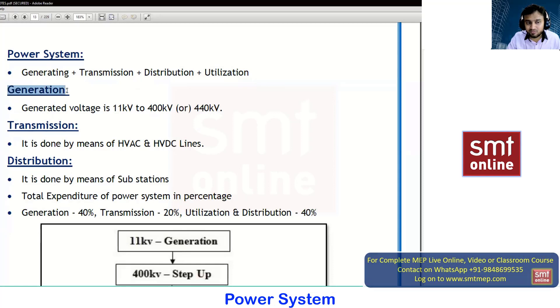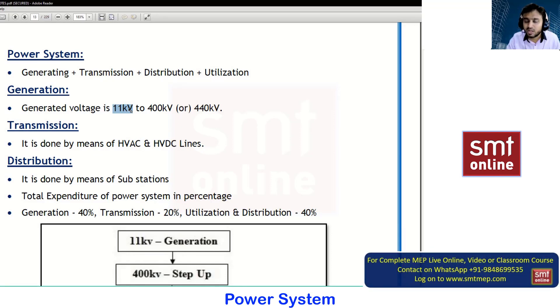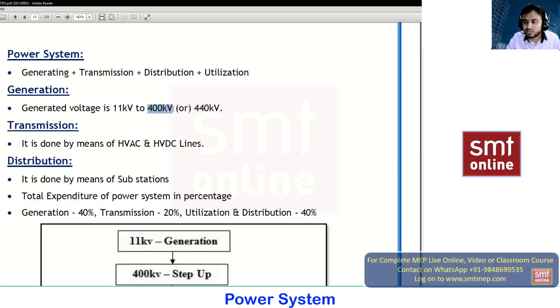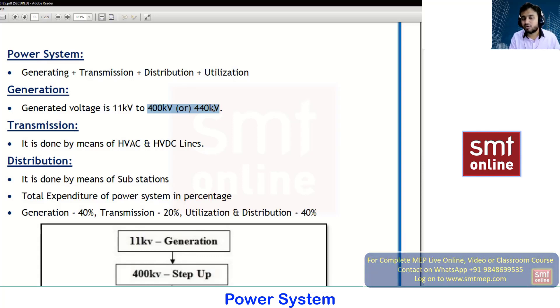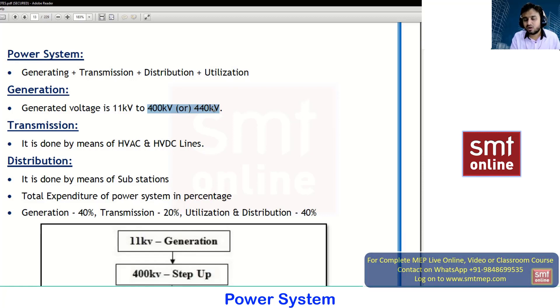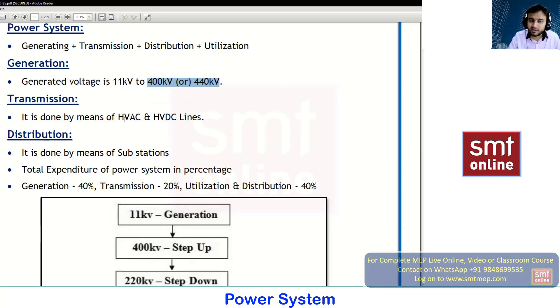On the generating side, the voltage will always be 11kV. It can be any type of plant — hydro plant, thermal plant, or nuclear plant — the voltage will be 11kV. With the help of a step-up transformer we step up the voltage to 400 or 440kV depending on the demand. If the supply is coming to a metropolitan city the voltage value will be high; for remote areas it can be maintained at 33kV, 66kV, or 132kV depending on the demand and load.